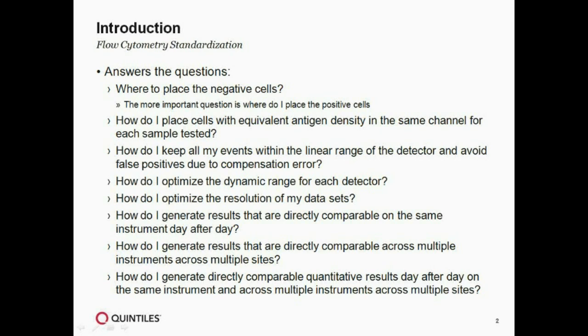Now that we know we want the positive in the same place every day, we have to ask: how do we go about doing this? If I'm setting up the instrument every day, how do I make sure events aren't running off scale — where compensation error will cause false positives? How do I optimize the dynamic range for each detector? How do I know I'm getting the best performance? How do I optimize the resolution of my data, and generate results that are directly comparable on the same instrument day after day, or across multiple instruments?